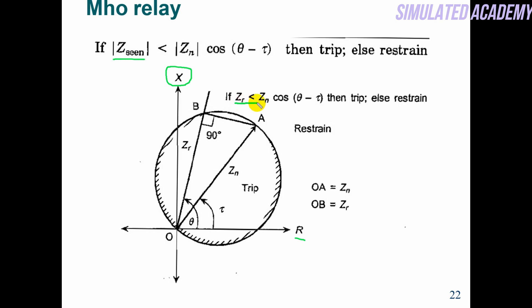The condition is Z_seen < Z_n × cos(θ − τ) for tripping; otherwise it restrains. OA is Z_in × cos(θ), which is a preset value, and Z_r is the apparent value that the relay measures at some instance. τ is the maximum torque angle and θ is the angle between voltage and current. Z_n is the diameter of the circle. Compared to simple impedance relay where Z_n was the radius, in this case the circle is much smaller.